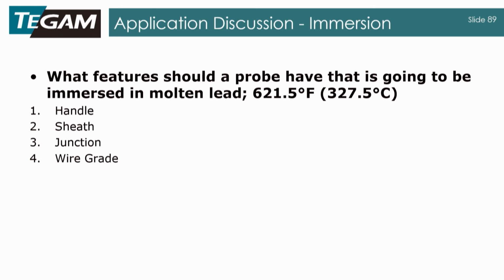For the wire grade, you're going to want to use thermocouple grade wire since you're going to such a high temperature. For insulation, and in this case I'm talking cable insulation, you're going to want something probably stainless steel. Anything that's going to be close to this or the heating elements for this molten lead, you don't want your cable melting away on you. And TC type K should be fine. As we talked about before, K starts to drift a little bit over 500 degrees C, but since we're at 327, we should be okay with the K-style thermocouple. And lastly, the probe tip, probably for this application, the immersion would be the best type.